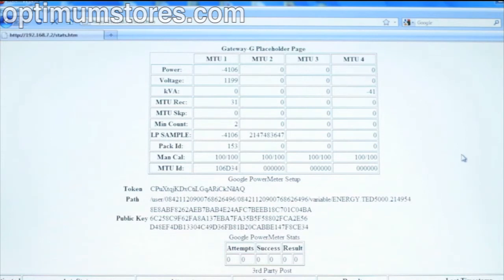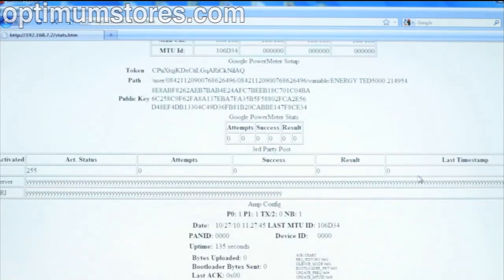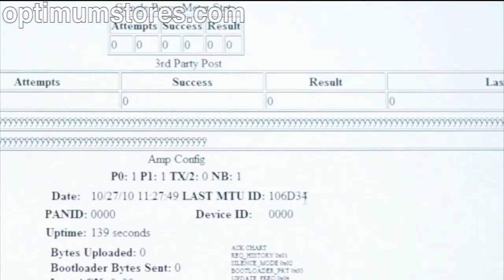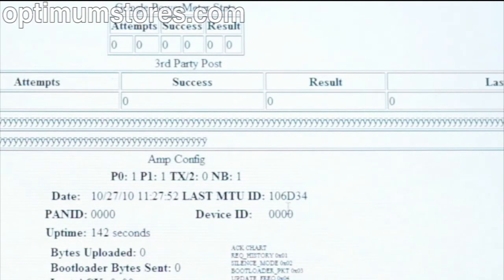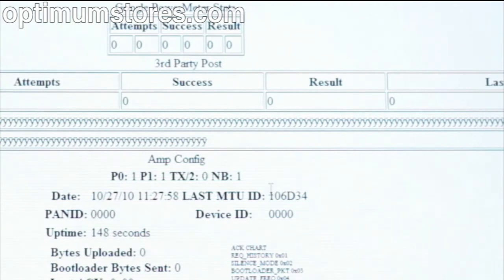But before proceeding to the next video, look down the page at the last MTU ID line. If this is also all zeros, you do have a PLC problem. If the number is an ID that differs from your saved MTU ID, maybe you have a typo. Note the number returned for last MTU ID and enter it into your system settings wizard.